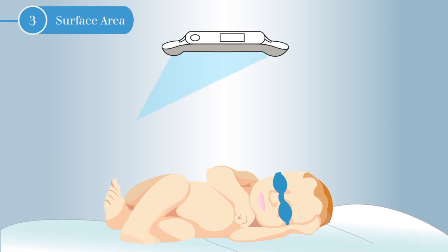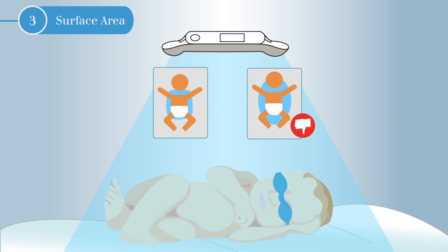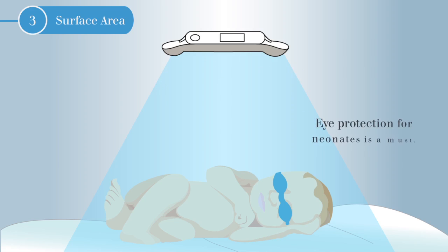For the third consideration, let's look at surface area. This means exposing as much of the neonate skin as possible to phototherapy. Widespread coverage increases the speed of bilirubin clearance in relation to bilirubin production. To protect against retinal damage, eye protection for the neonates is a must, and clothing should be minimal.